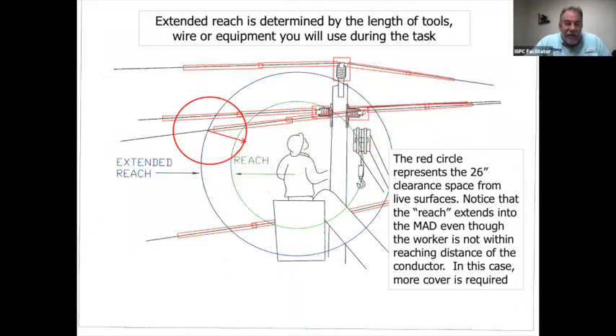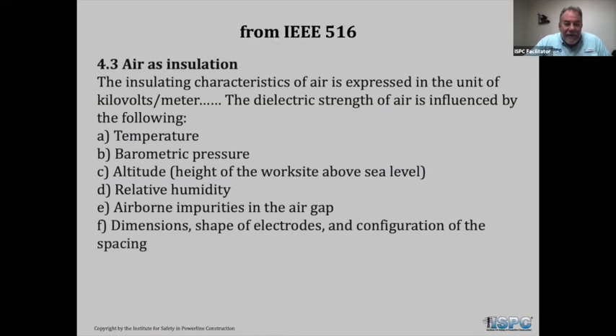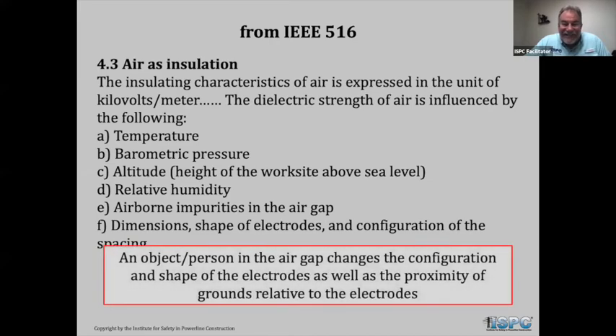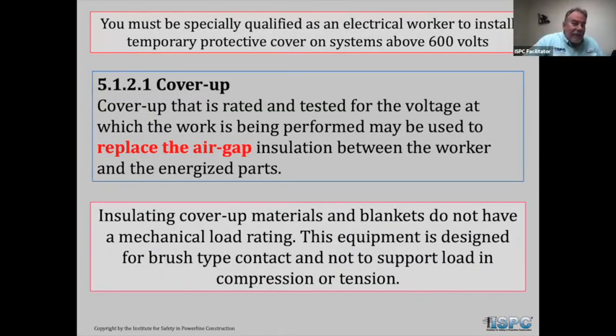All right, moving on very quickly, talking about the minimum approach distances. How do we get these numbers? It came from the IEEE 516. Cover up is rated and tested for the voltage at which the worker is using. It's used to replace the air gap insulation between the worker and any energized parts.